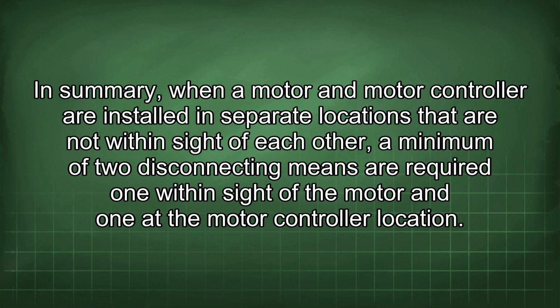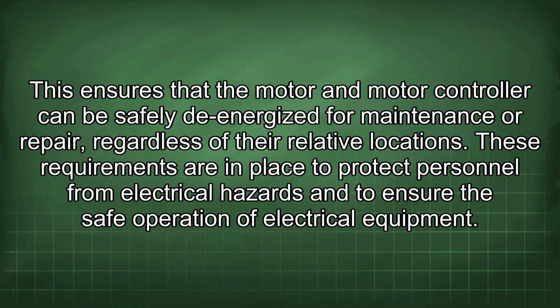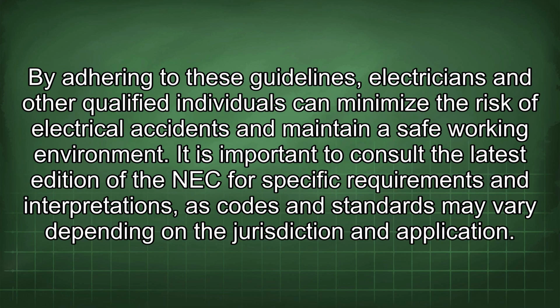In summary, when a motor and motor controller are installed in separate locations that are not within sight of each other, a minimum of two disconnecting means are required, one within sight of the motor and one at the motor controller location. This ensures that the motor and motor controller can be safely de-energized for maintenance or repair, regardless of their relative locations. These requirements are in place to protect personnel from electrical hazards and to ensure the safe operation of electrical equipment. By adhering to these guidelines, electricians and other qualified individuals can minimize the risk of electrical accidents and maintain a safe working environment.